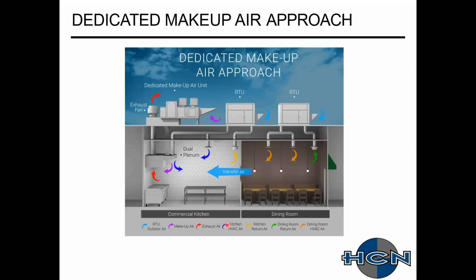And here's an example from a manufacturer of basically their dedicated makeup air approach. In this typical design, we're looking at a hood system where makeup air is providing about 80% of the air. They're looking for about 20% transfer air coming in from the rooftop units. And in this design, they're using a dual plenum configuration. With their dual plenum configuration, they promoted a little bit better capture for this PSP, because typically with a PSP design, you have to minimize the width of the PSV. Once you start getting bigger PSPs, anything over 14, 16, 18 inches, you're getting a lot more diffusion into the space versus it being captured back into the hood. So this promoted almost a bit of an air curtain. That makeup air would hug, but then the exhaust hood would do its job and pull it in, so you'd have less diffusion.